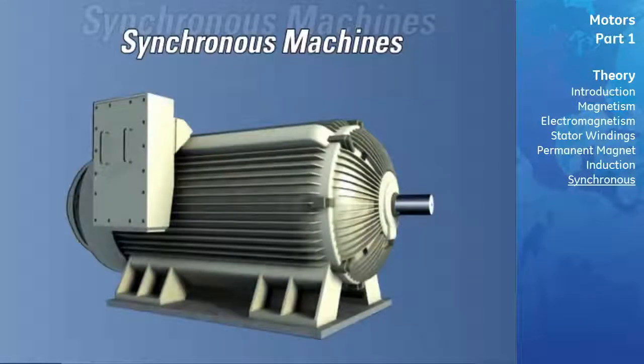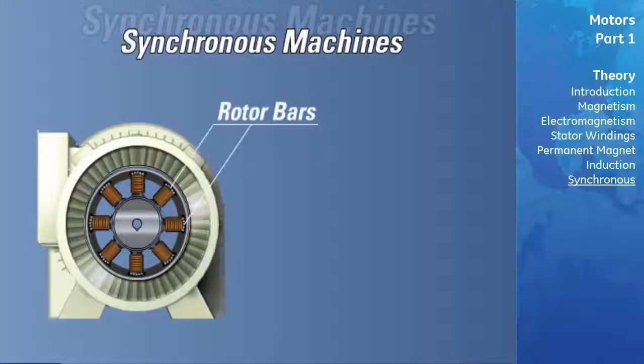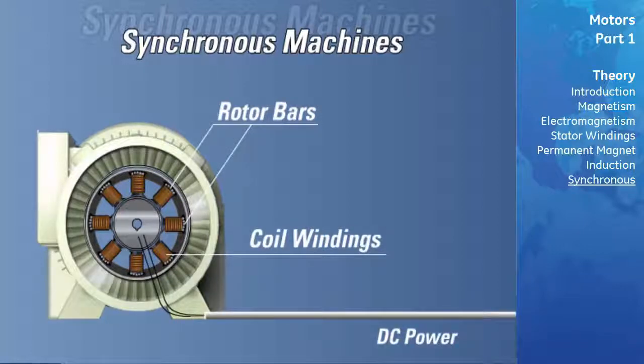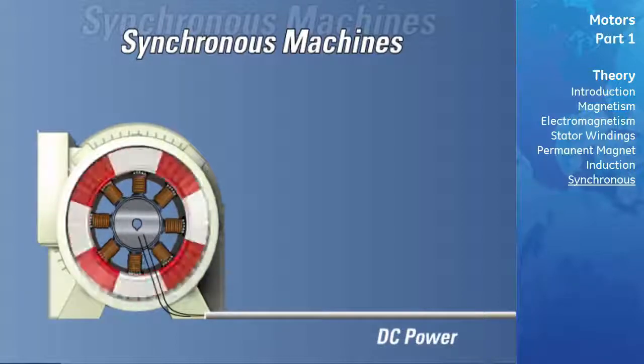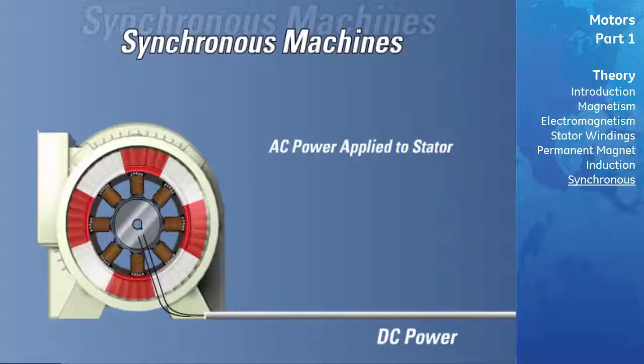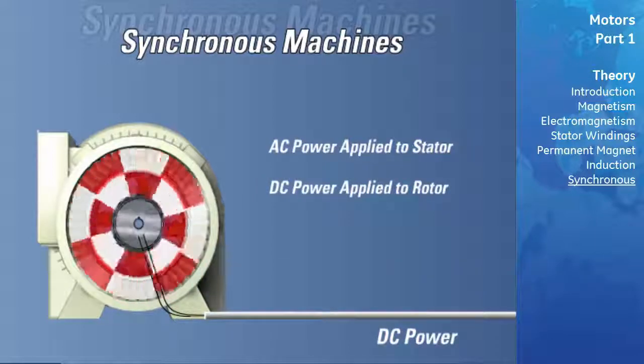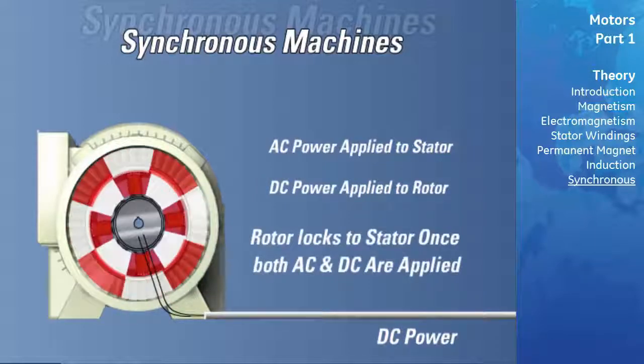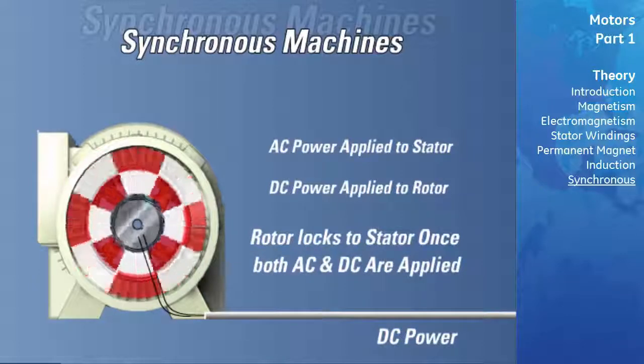Larger motors tend to be synchronous machines. The rotor of the synchronous motor is constructed similar to that of the squirrel cage rotor; in addition to rotor bars, coil windings are added. These coil windings are connected to an external DC power source through a slip ring and brush assembly. During a start, AC is applied to the stator and the motor accelerates as an induction motor would. Once it reaches maximum speed, DC is applied to the rotor coils, producing a strong, constant magnetic field in the rotor. This field locks in step with the rotating stator field, so there is no difference in speed between the rotor and the stator's rotating field.